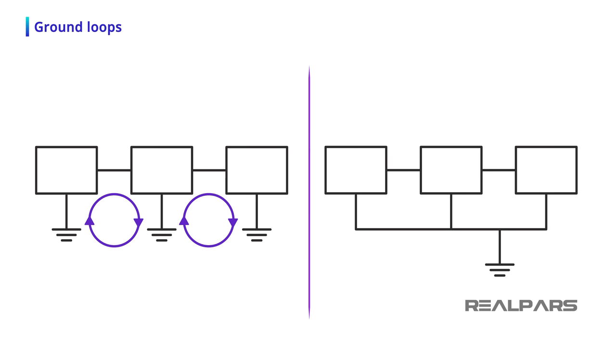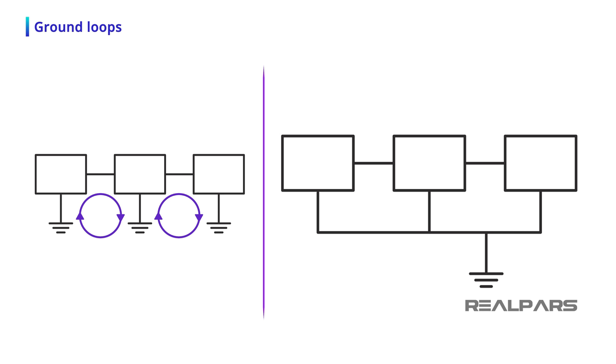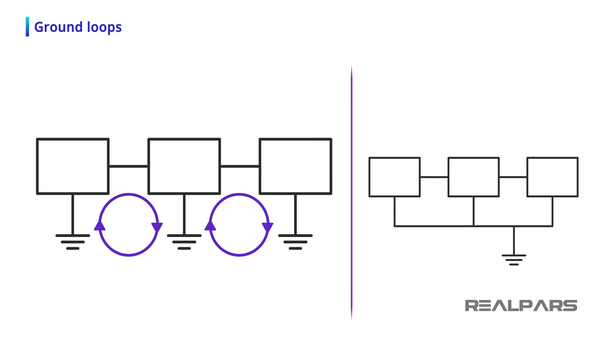In our example, ground loops can be avoided if all three devices are grounded together at one point. This type of grounding is referred to as star point grounding. Unfortunately, in large industrial plants, multiple point grounding is the reality, and the possibility of ground loops is high. With so many connections referenced to ground within a facility, the chances of needing more than one ground point are great.